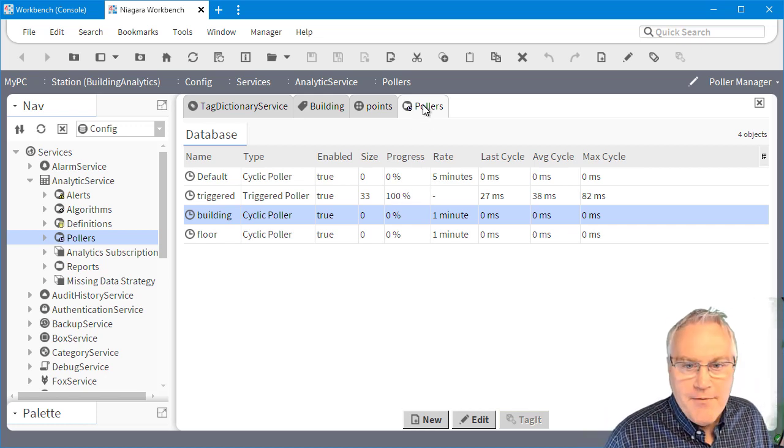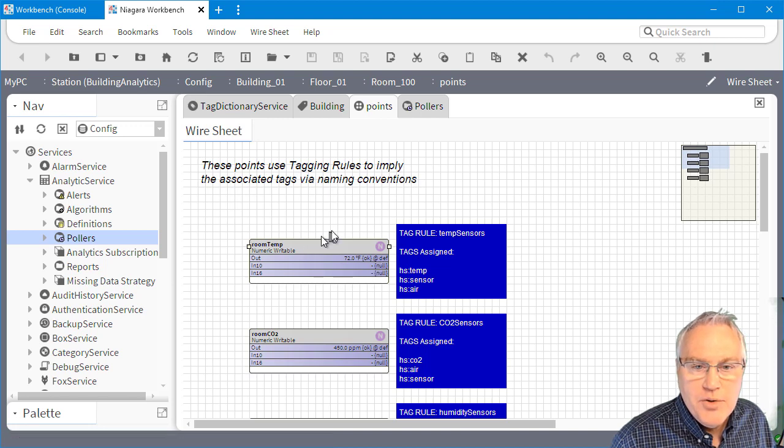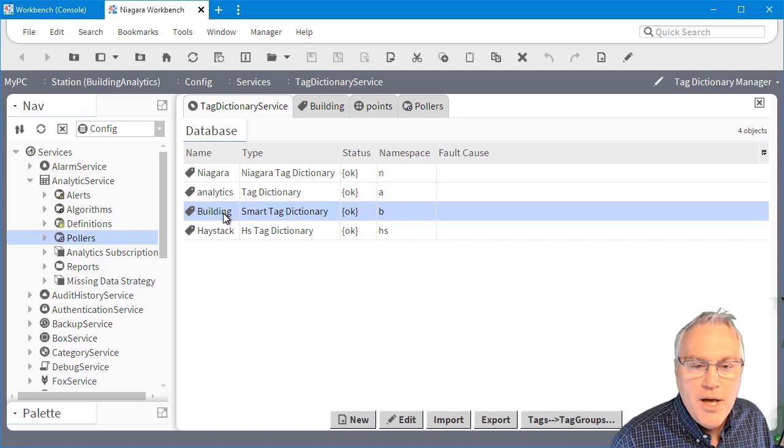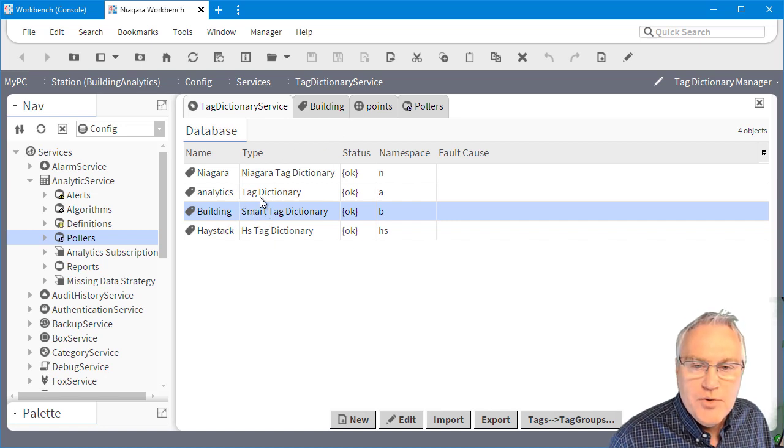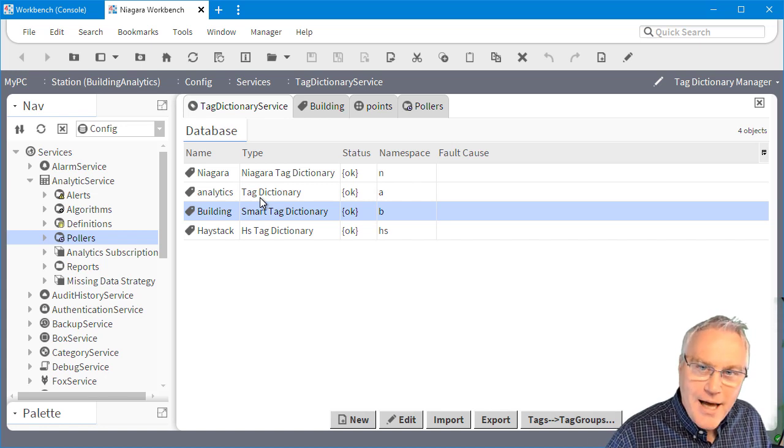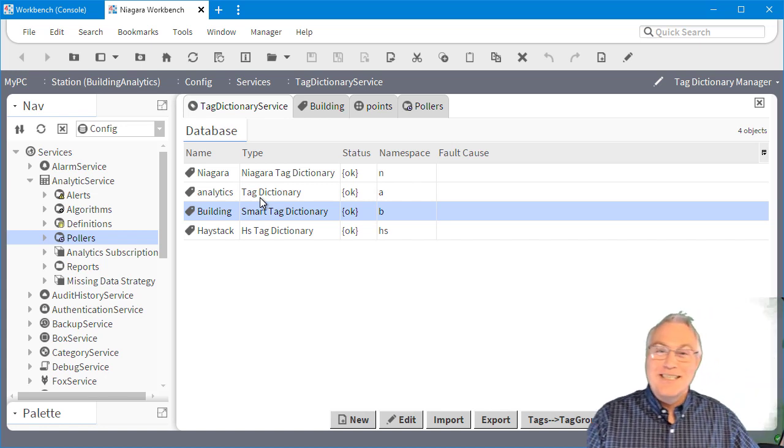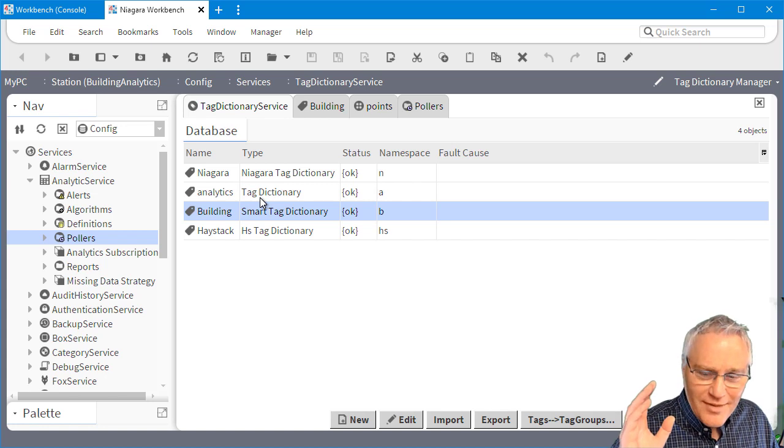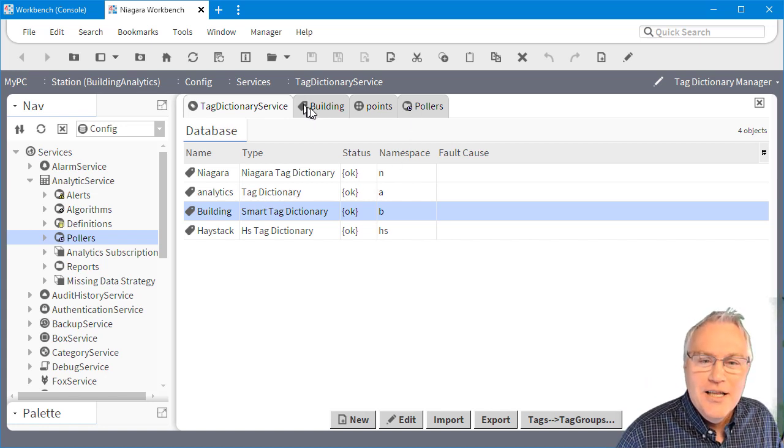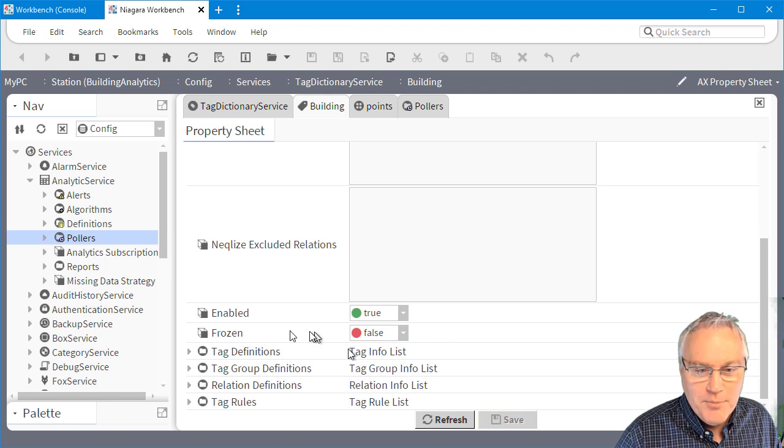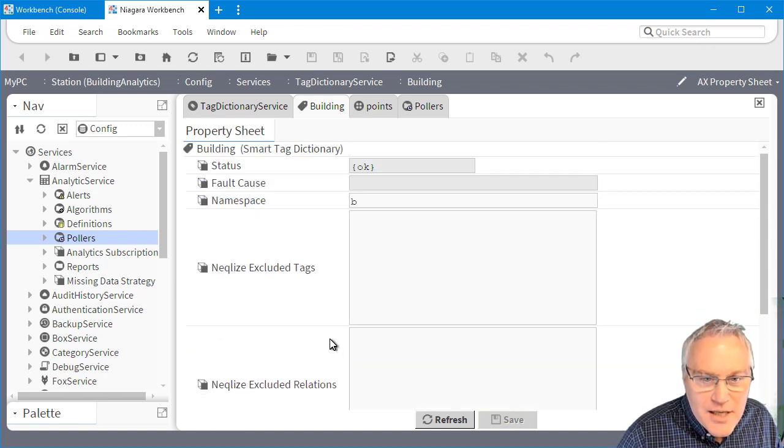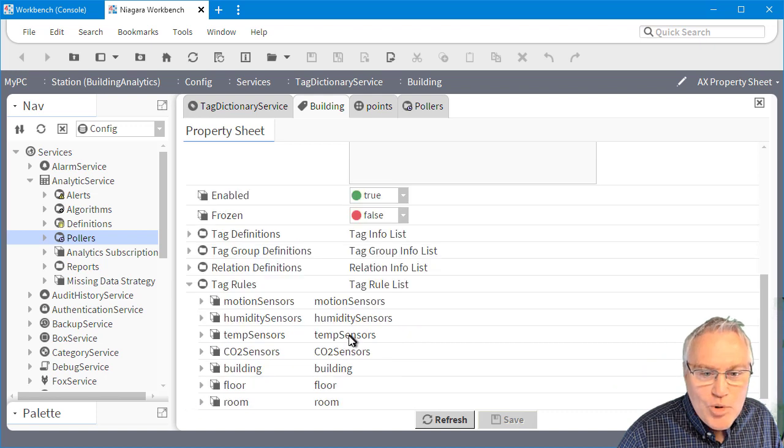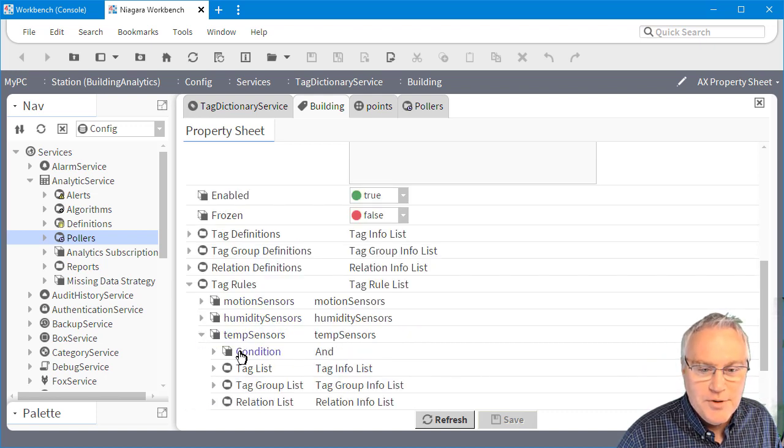I have a series of points that I'm going to tag. I actually use the tag dictionary service, so I have a series of rules that will execute. In prior stations, I told you never to direct tag, and then I would direct tag in the demo. So I ate my own dog food. There's rules in this station that I use to actually apply or imply those tags. So if you come down here and you look at some of my tag rules, you'll see that I have motion, humidity, temperature.